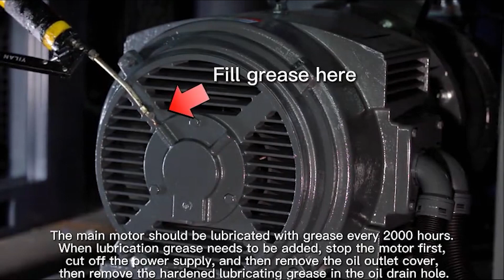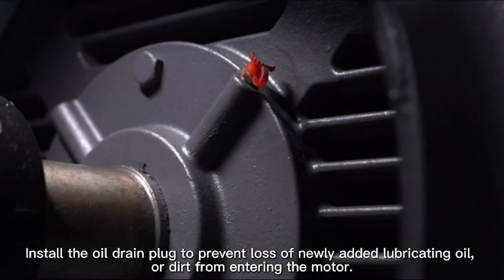Gel lubrication is recommended. Generally, it will not leak from the oil outlet, but if it leaks, stop adding oil immediately. Both ends of the motor housing have oil filling holes and oil drain plugs. Install the oil drain plug to prevent loss of newly added lubricating oil or dirt from entering the motor.